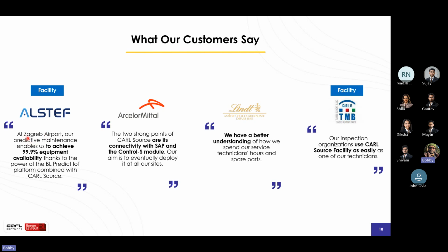They did an experiment in Zagreb Airport in Europe, and achieved 99.9% equipment availability when they used CAL BL Predict. It was able to tell before failures if a motor was running in two phases, for example, in the conveyor. They got alerted, the technician goes to it, uses his multimeter, the tong meter, and says 'Yep, I can see a problem.' He fixes it within the small break he gets, and the motor never has to be replaced - so there's no breakdown. You got it fixed.